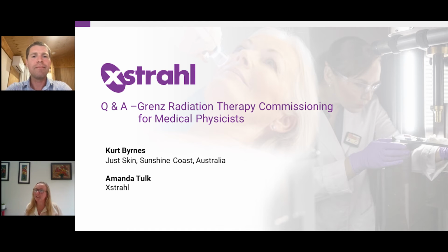Okay, so secondary to that, which chamber would you recommend for somebody who's about to start commissioning Grenz rays on one of their devices? Well, the PTW 23342 and the 23344 are very good. I was lucky enough to have one of those because a lot of the literature out there uses both of those. So the AAPM documents and the new TRS 398 have those geometry factors. But apart from that, I would really like to try the Xstrahl X100. That's meant to be used for the 50 kV intraoperative breast treatments. It's got a large volume and a thin window with no stem effect. I think that one would work really well in air. And I know Xstrahl has some other thin window chambers that not many people in Australia use, but I think they would probably work well.